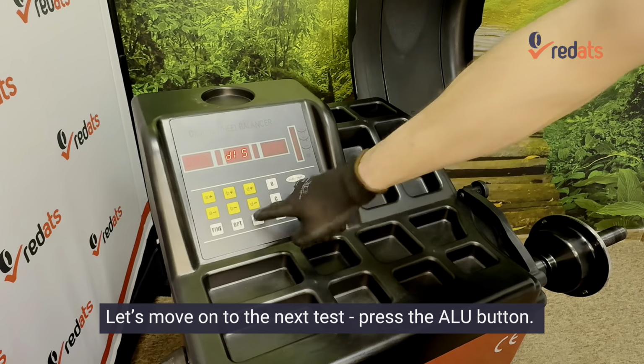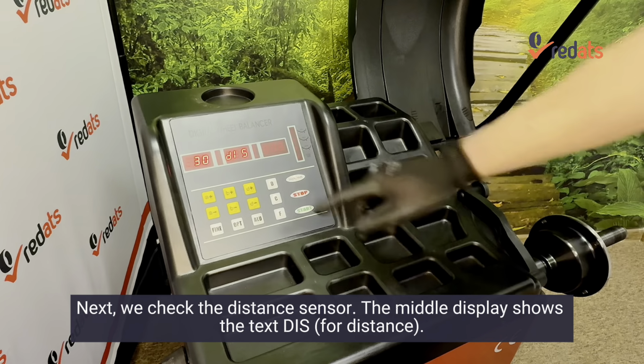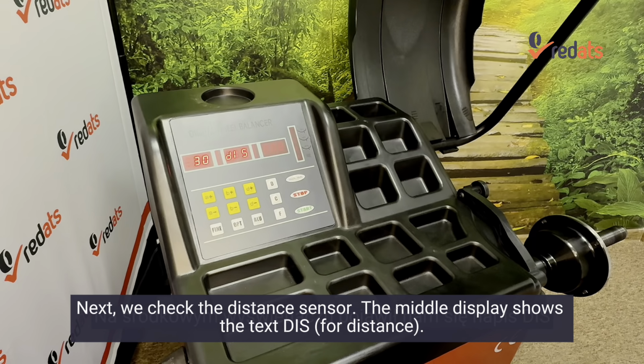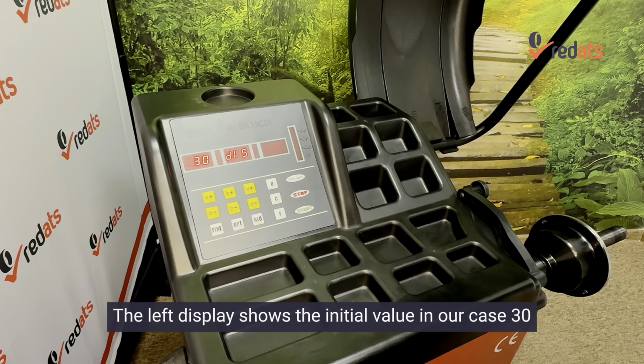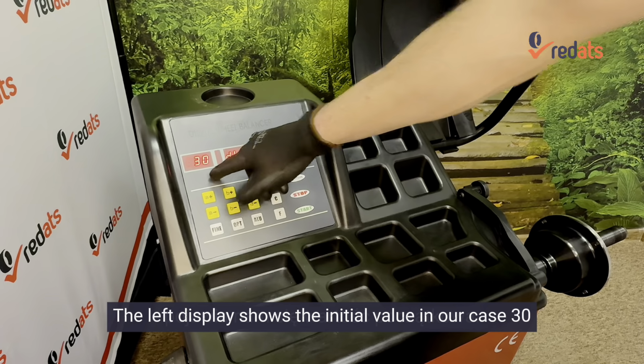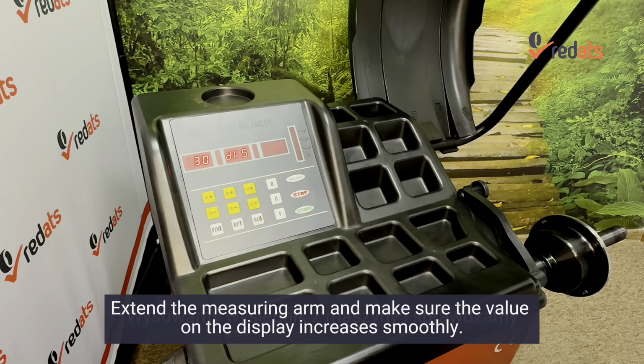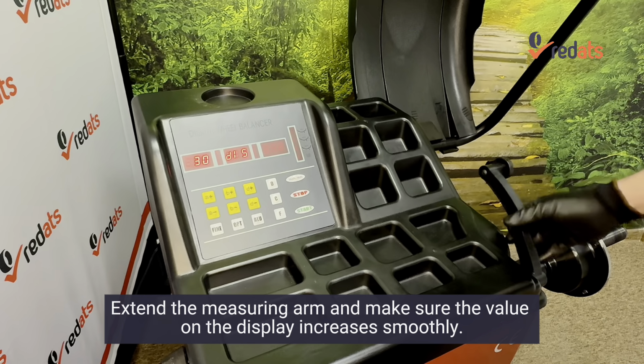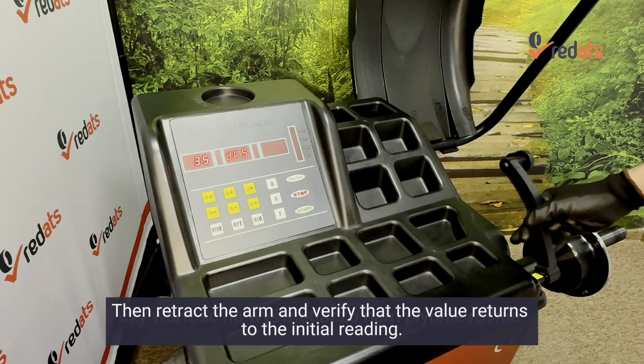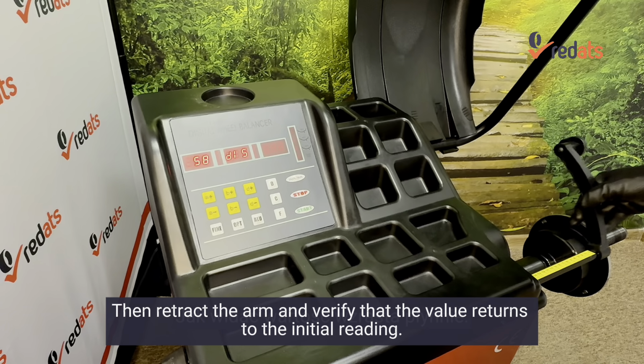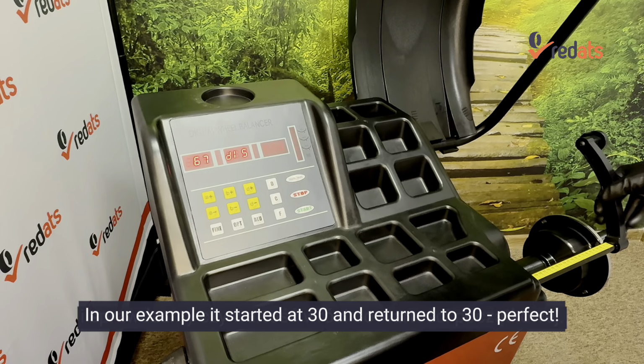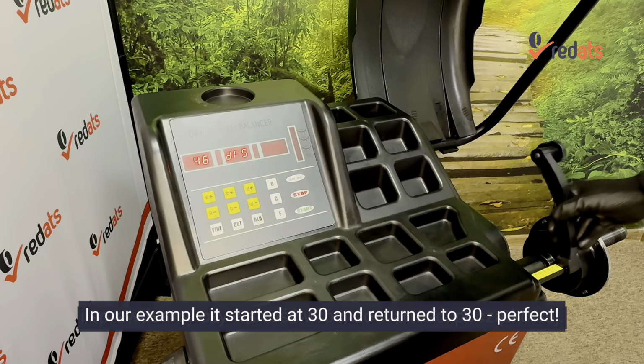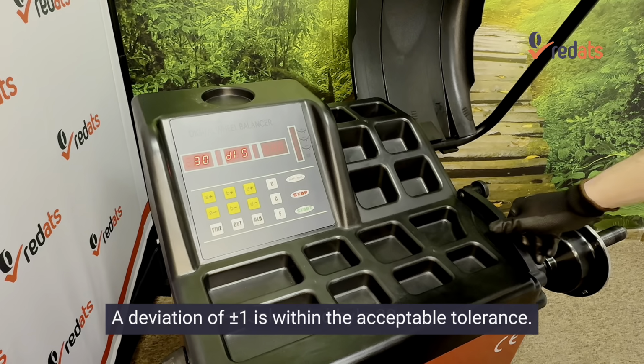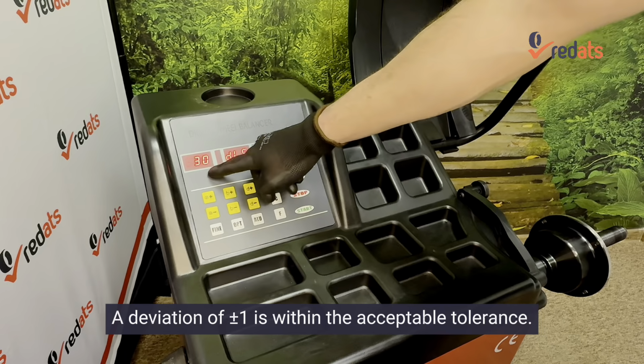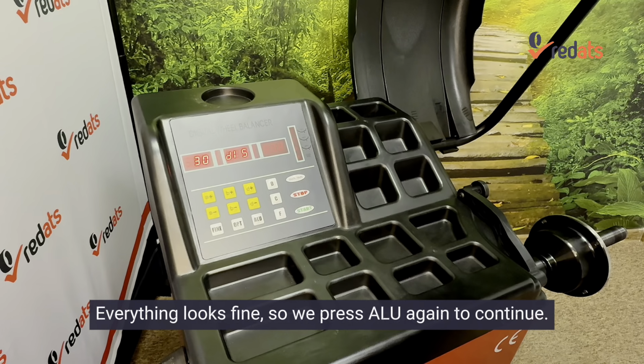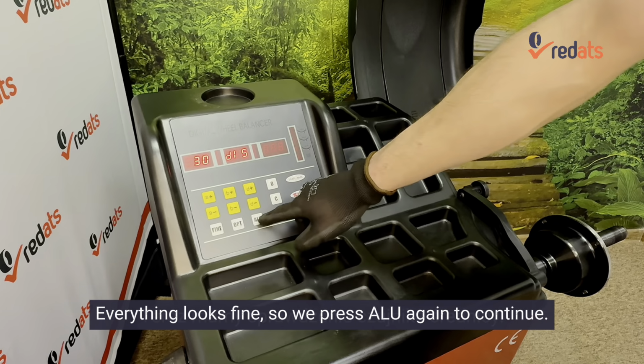Press the ALU button. Next, we check the distance sensor, and the middle display shows the text DIS for distance. The left display shows the initial value, in our case 30. Extend the measuring arm and make sure the value on the display increases smoothly. Then retract the arm and verify that the value returns to the initial reading. In our example, it started at 30 and returned to 30. Perfect. A deviation of plus or minus 1 is within the acceptable tolerance. Everything looks fine, so we press ALU again to continue.